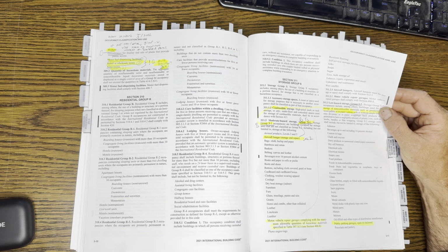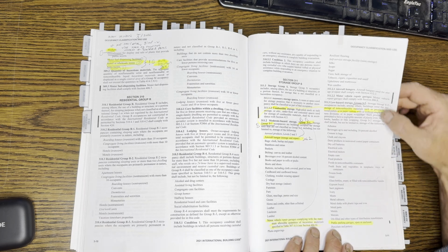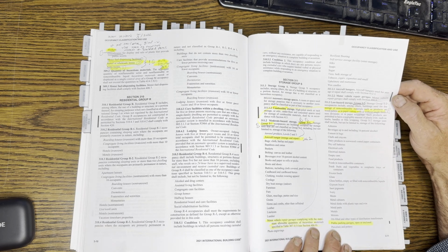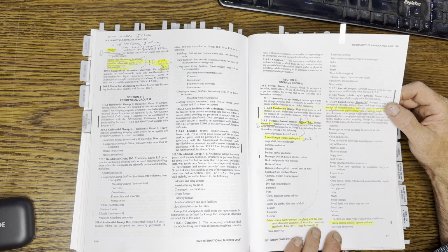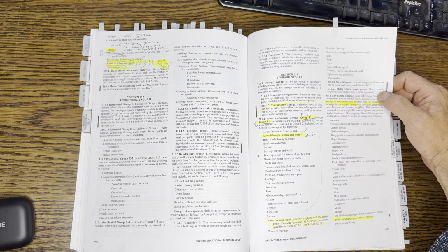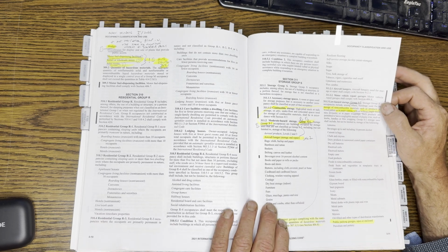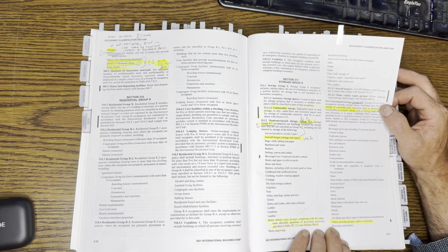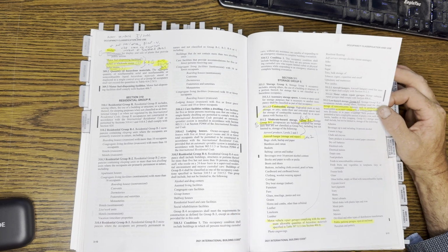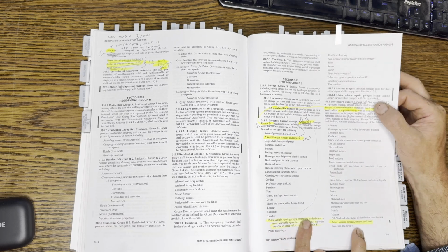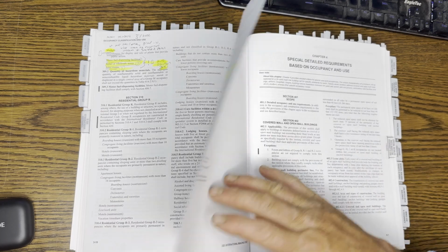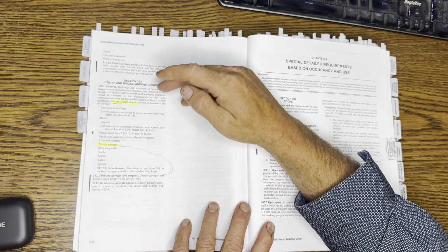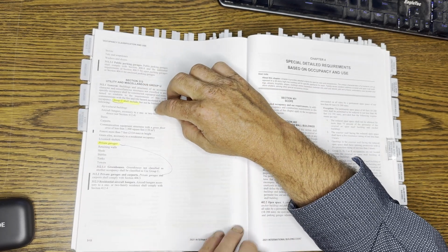This may come up occasionally, not often. I usually am more conservative in the facilities I manage. I usually default to an S1 just for a little more conservatism, and it gives you more flexibility. But keep in mind, if you're doing a parking garage, it's a Group S2, but you can also have this as a Group U if it meets certain parameters. Benefit of Group U is you don't need suppression and a lot of other more expensive stuff.